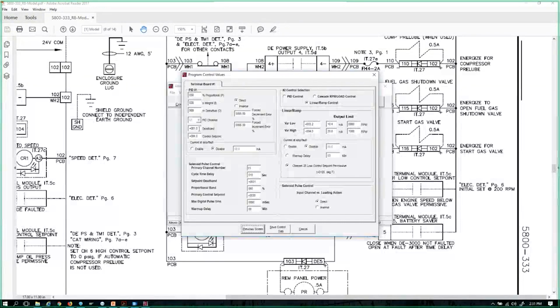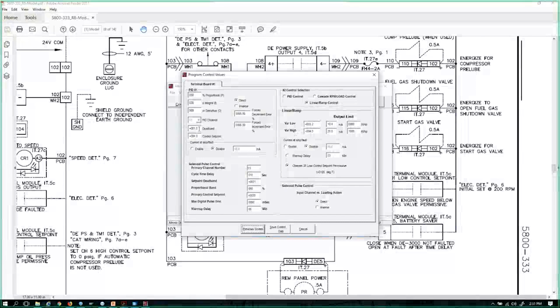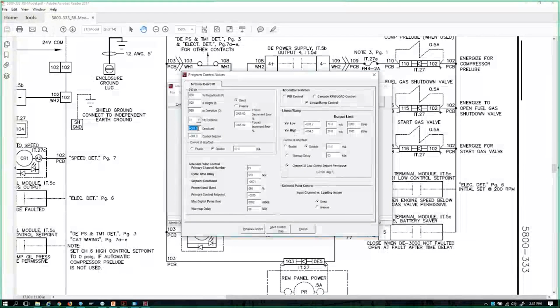We have a deadband selection. Now some people, when they get up into really high pressures, like to use deadbands. In my case, if I'm down around 50 pounds as my control set point, or under 100 pounds, generally you're going to see me, if I'm tuning one of these systems up, select 0 pounds as my deadband. I want the system always floating. So what is a deadband? If I put a set point in here, and let's say I want to control at 40 psi.